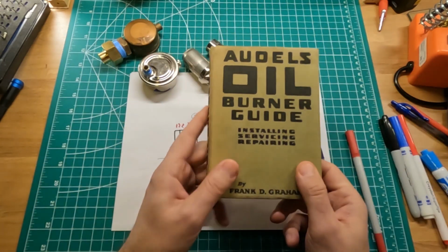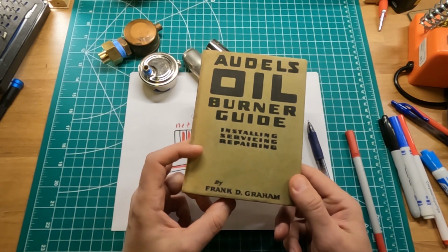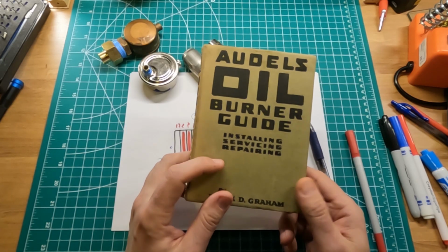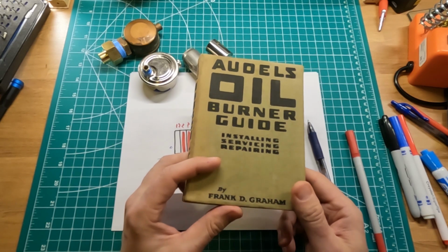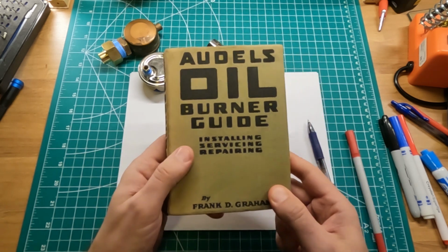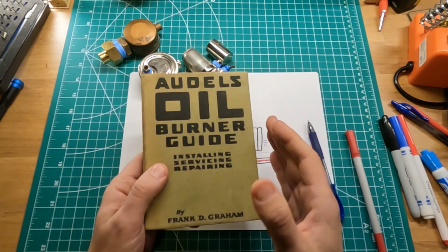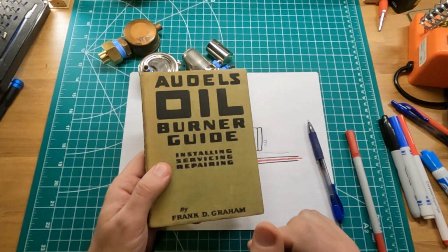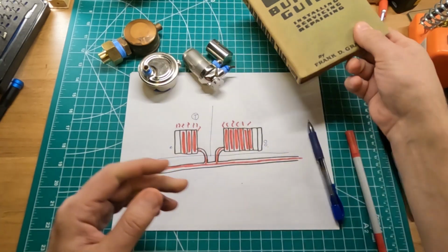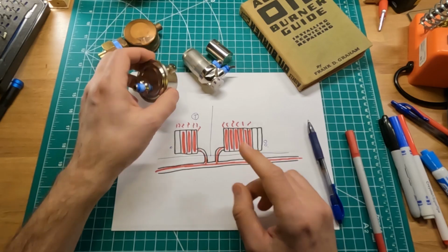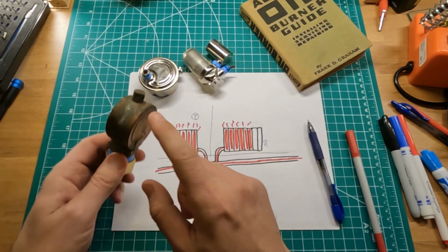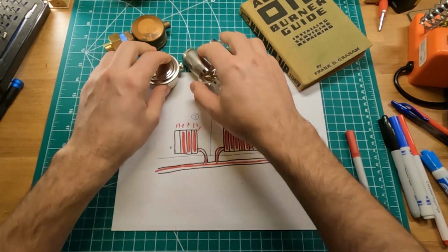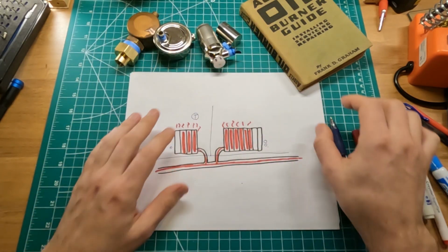Incidentally, this is a fascinating, great book, by the way, if you are into steam heat. It talks about this, that if you have an oil burning or any sort of modern boiler that has either oil or gas, so that means it operates on an on and off principle, then that means you do have to properly balance your system. You have to get adjustable air vents. You will never be able to do it with those that have preset opening. All right, so that's our theory.